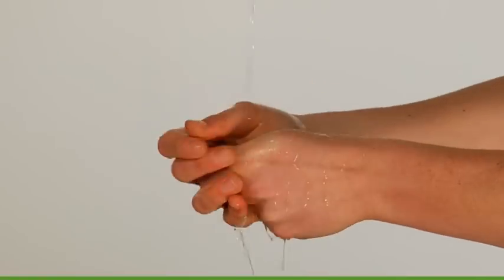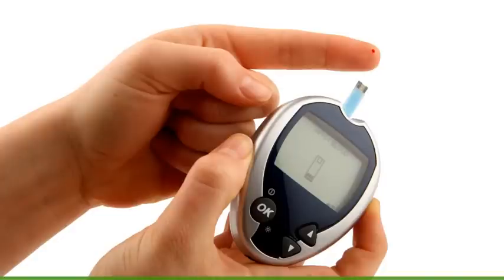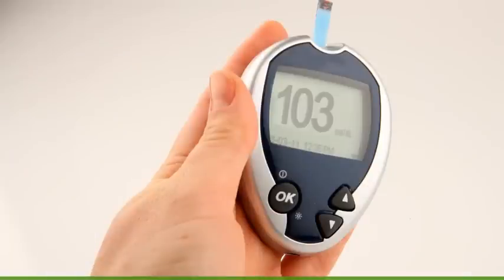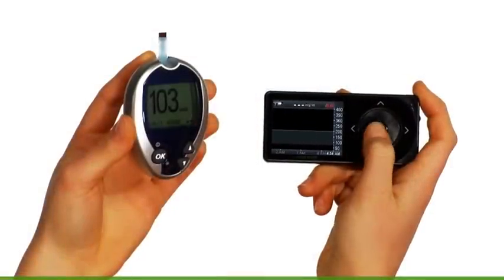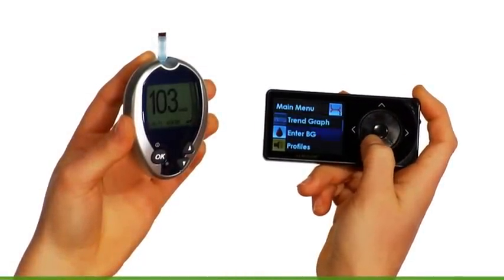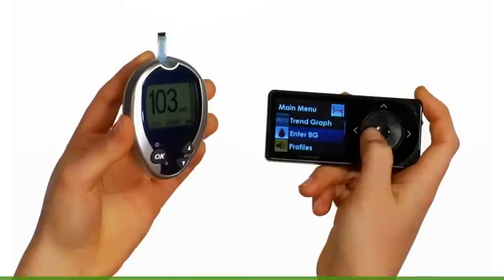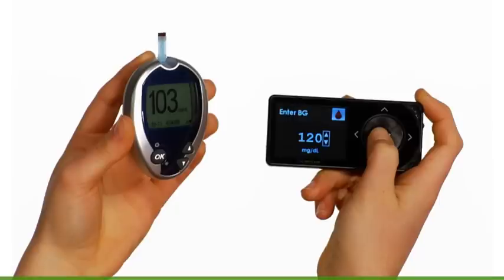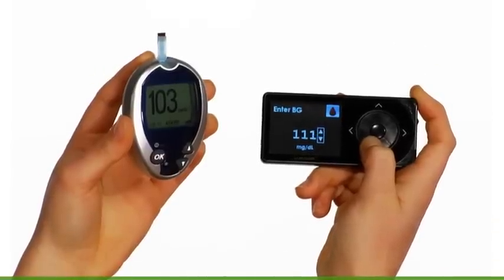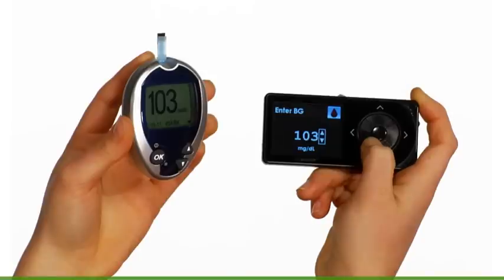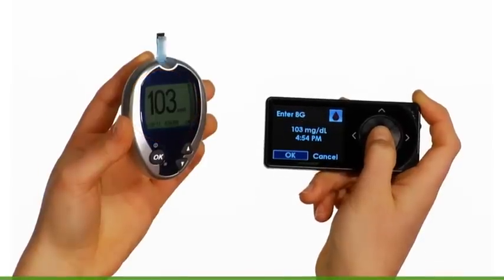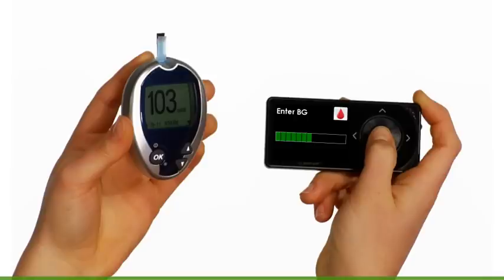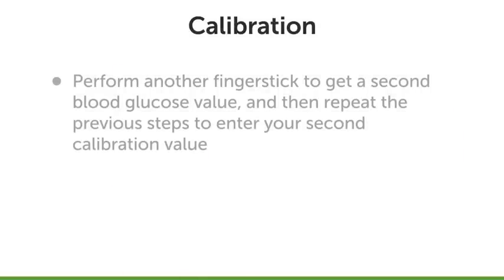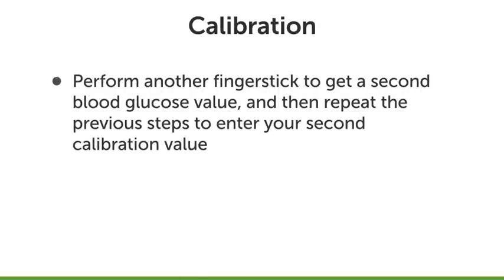Next, wash and dry your hands. Perform a fingerstick blood glucose reading with your blood glucose meter. Enter the exact blood glucose value into your Dexcom G4 Platinum receiver within 5 minutes of performing the fingerstick. To enter the value, press Select to get to the main menu. Press the down button to highlight Enter BG. Press Select to choose this option. Initially, the default glucose setting will be at 120 milligrams per deciliter. Press the up or down buttons to enter the exact blood glucose value from your blood glucose meter into the receiver. Press Select. Confirm the calibration value is correct. If yes, press the Select button to accept the calibration entry. Perform another fingerstick to get a second blood glucose value, and then repeat the previous steps to enter your second calibration value.